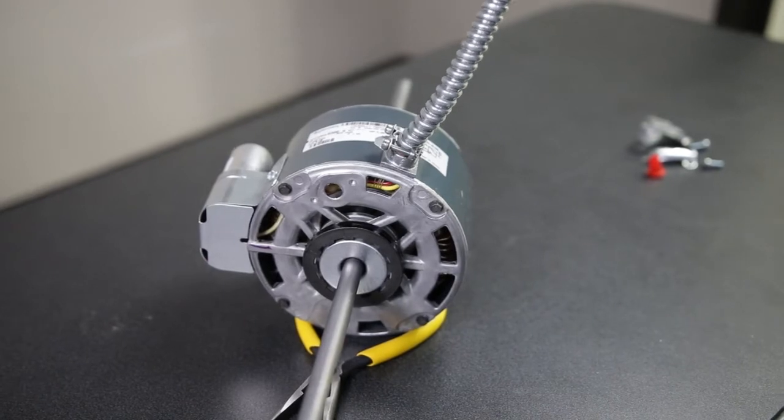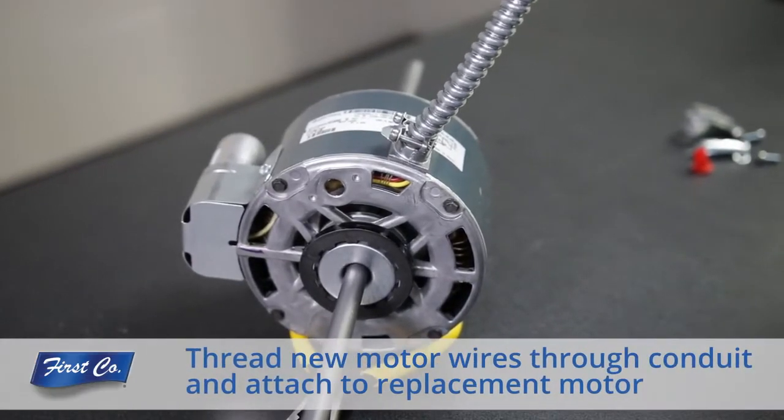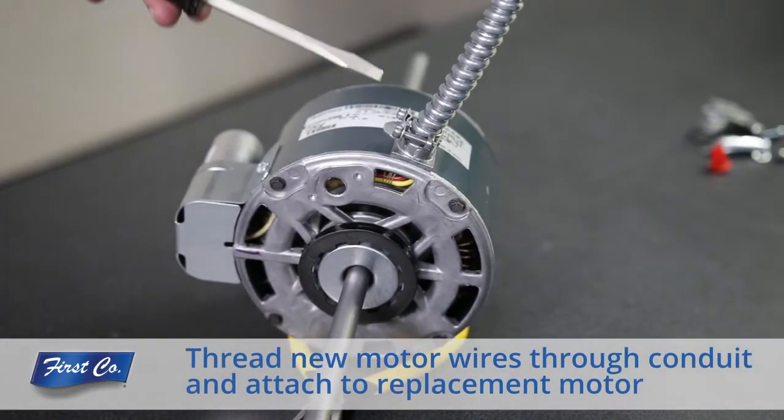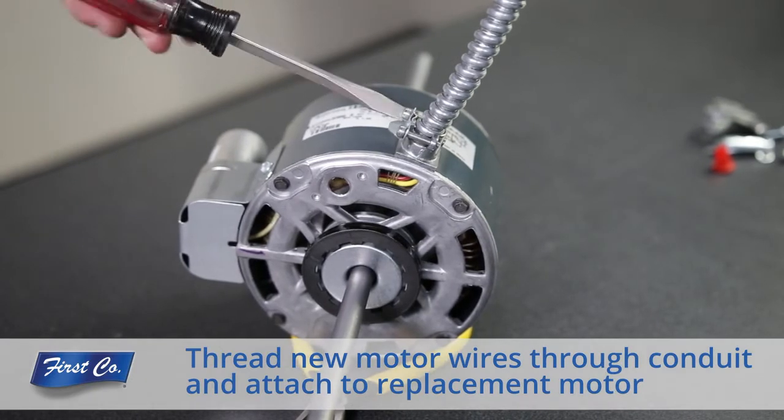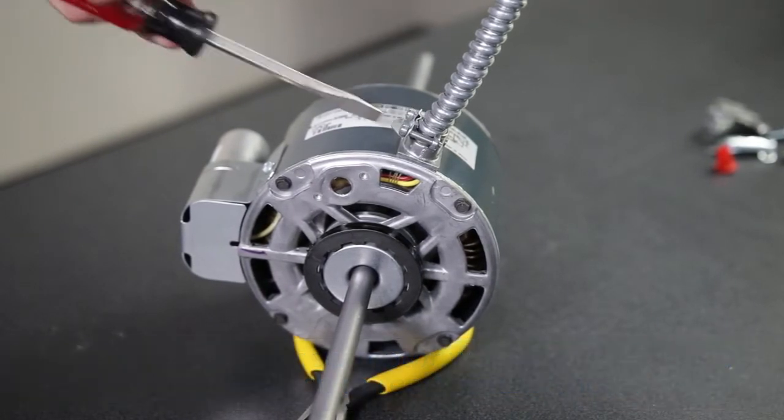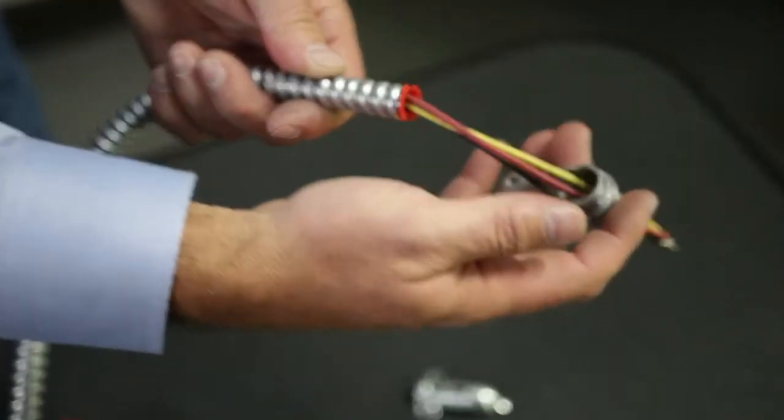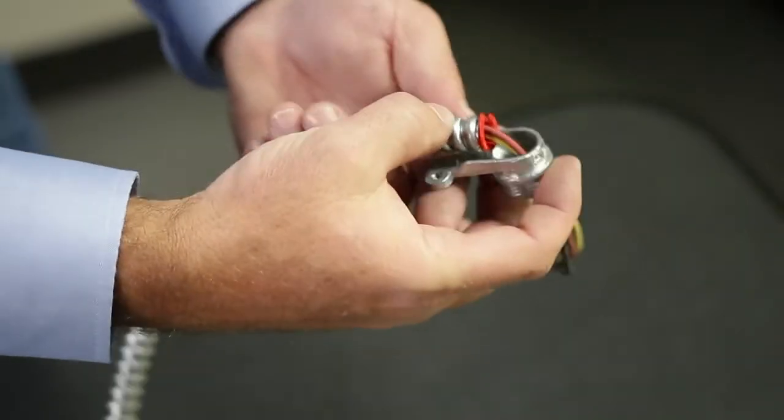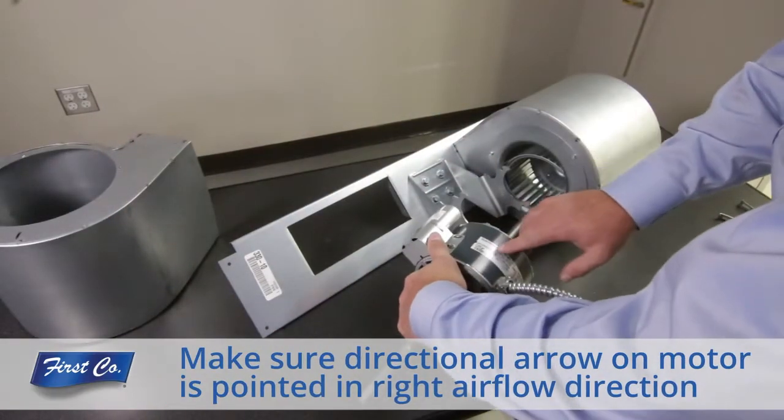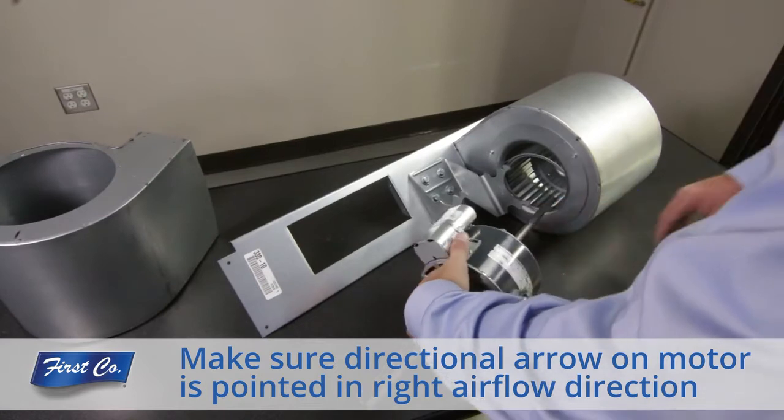Using the flexible conduit removed earlier, thread the motor wires through the conduit. Before installing the replacement motor, make sure the directional arrow on the motor is pointed in the right direction of airflow.